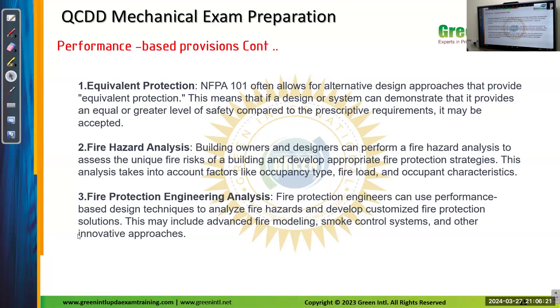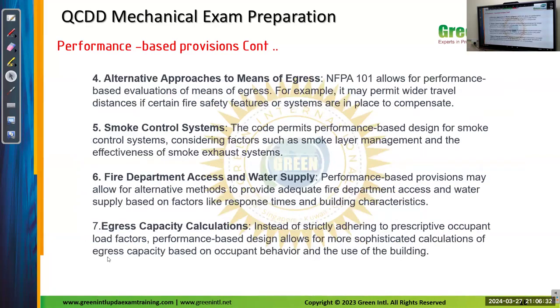Fire protection engineering analysis. This is a similar one. Develop customized fire protection solutions. This may include advanced fire modeling, smoke control systems, and other innovative approaches. Alternative approaches to means of egress. NFPA 101 allows for performance-based evaluations of means of egress. For example, it may permit longer travel distances if certain fire features are in place to compensate.